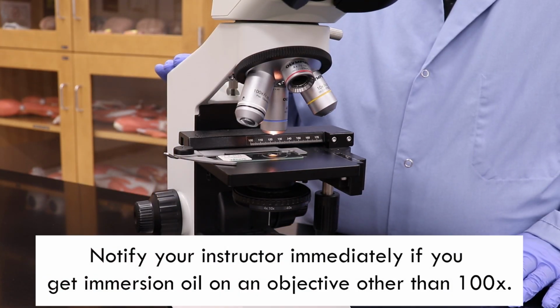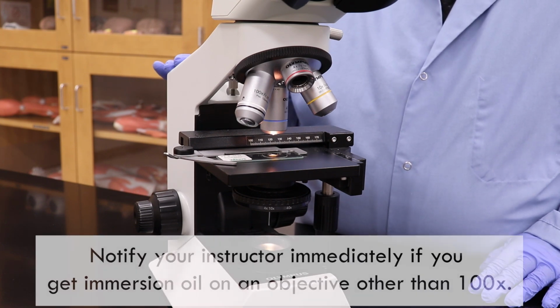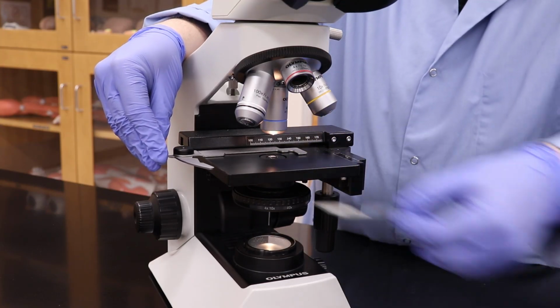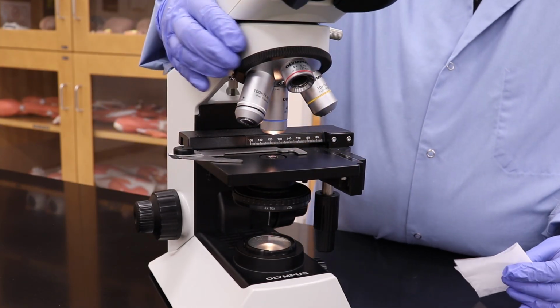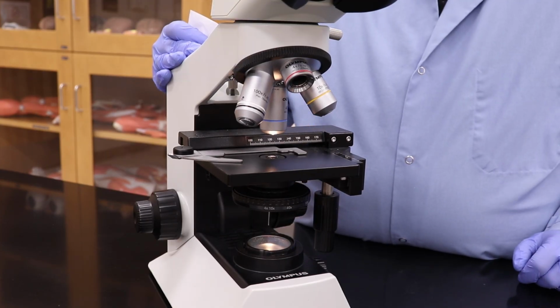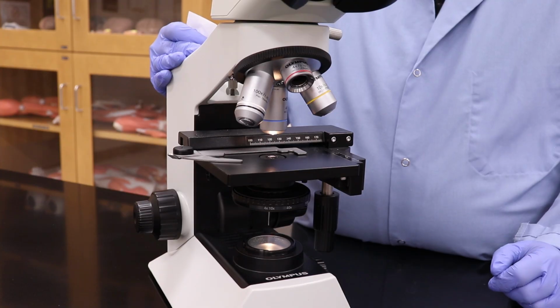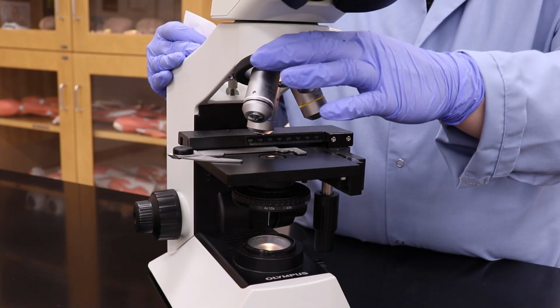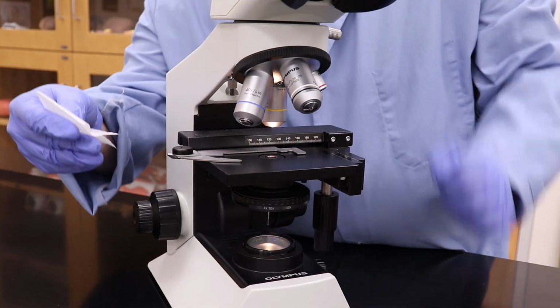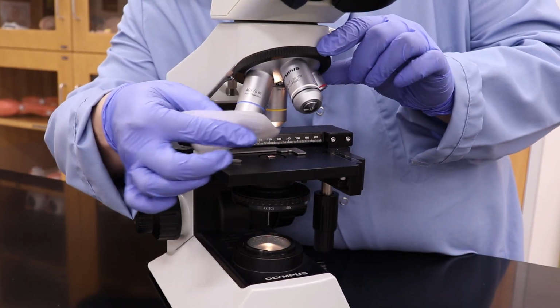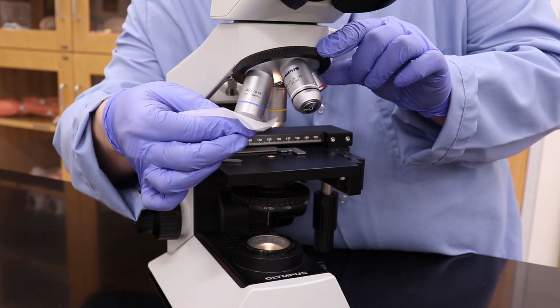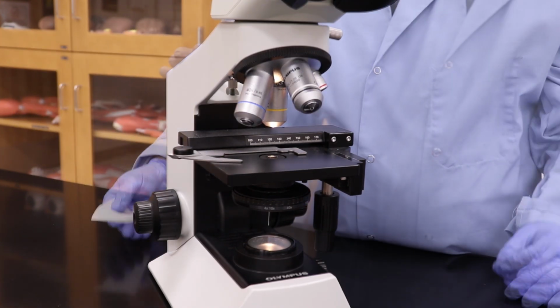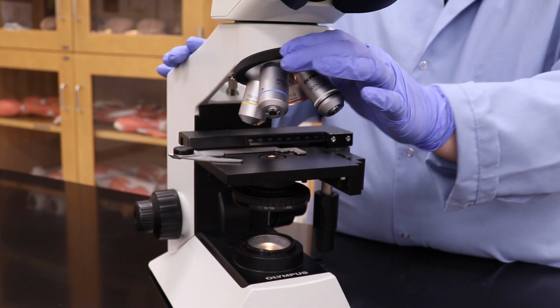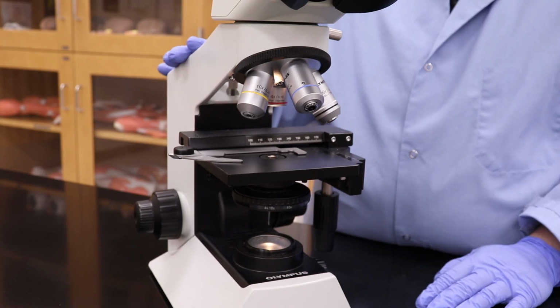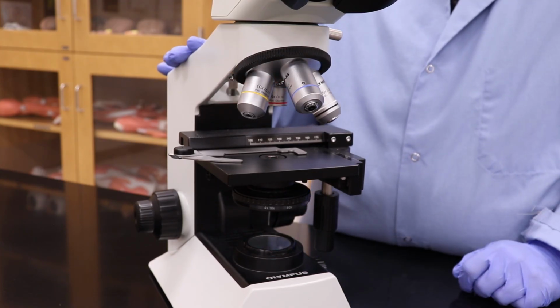Make sure to not get any immersion oil on any other objective. Immersion oil will damage other objectives other than the 100x. Now we will remove the slide with the lens oil for cleaning later and move on to cleaning the other objectives. The other objectives on the microscopes you'll be using here at PCC are 40x, 10x, and 4x. To get to them, just twist the nose piece again to bring them out. Cleaning these other objectives requires just a gentle swiping motion on the end of the objective. At this point, you can return the objective to the 4x, which is the shortest objective, using the nose piece, and then turn off the microscope. It's ready to be put away.